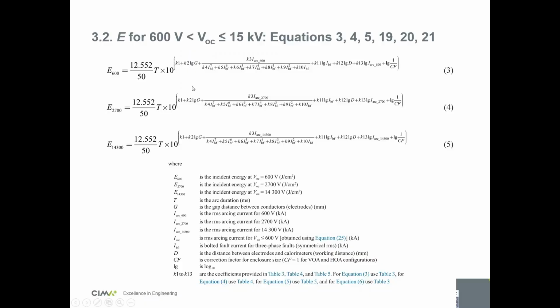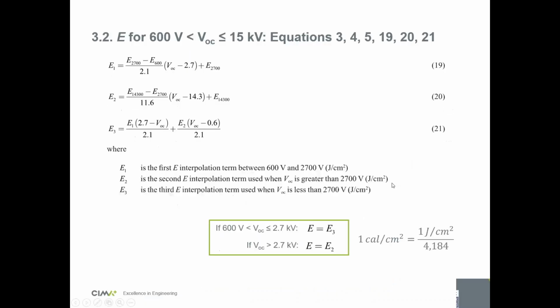So in these big formulas, you need to put your fault time. You need to put your distance between the conductors. You need your arcing currents from the other equations that we saw before. You need your voltage, fault current. You need your working distance. You need your correction factor for the enclosure size that you calculated before. And you need the coefficients K that come from some tables, and they're dependent on your electrode configurations.